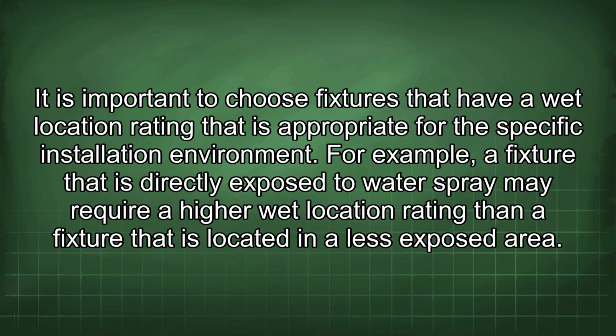It is important to choose fixtures that have a wet location rating that is appropriate for the specific installation environment. For example, a fixture that is directly exposed to water spray may require a higher wet location rating than a fixture that is located in a less exposed area.